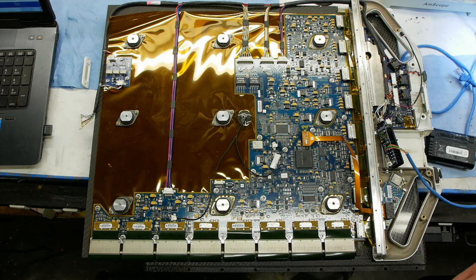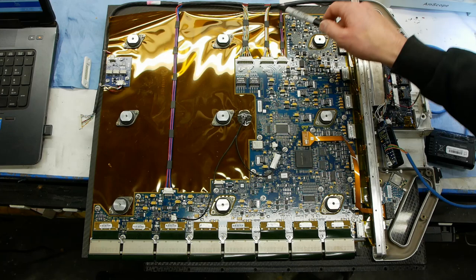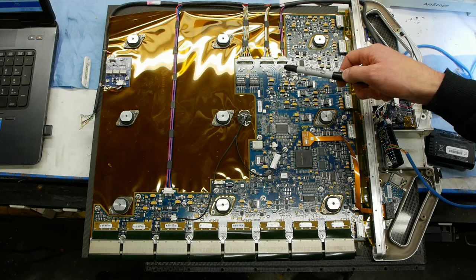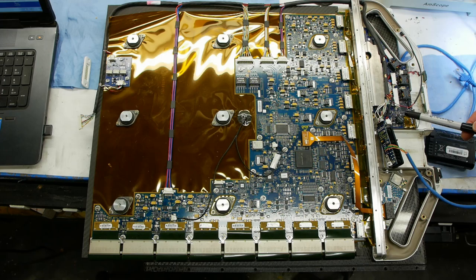This whole system requires quite a few different voltages, and all of these connections are supplying different rails from the power board up here. There's also an RS-485 connection that goes from the main board back to the power board to talk to the microcontroller up here to find out if the voltages are okay or how much power is being used, that sort of thing.